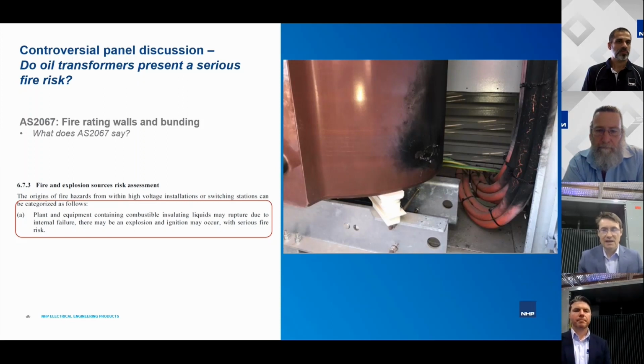So as we know, oil is a highly flammable material and has plenty of calorific energy in it. If a fire started in an oil transformer, it actually cannot even be extinguished by a fire brigade. They have to wait till the whole oil burns out. Now, the difference with the cast resin transformer is that the significant damage will occur while there is an electrical arcing fault still happening. But that is a very short event, because the electrical arcing fault is going to be cleared by upstream protection in generally less than a second.